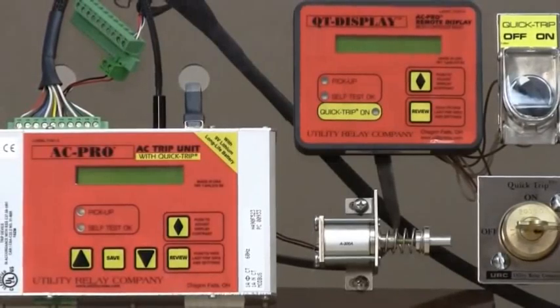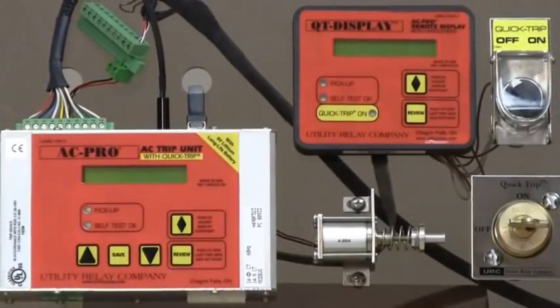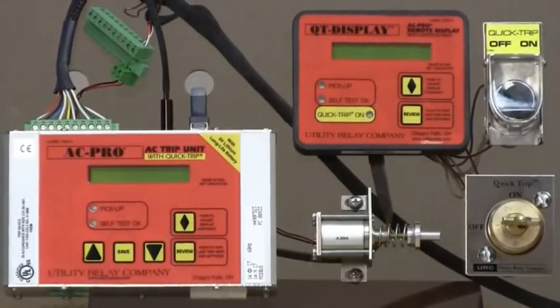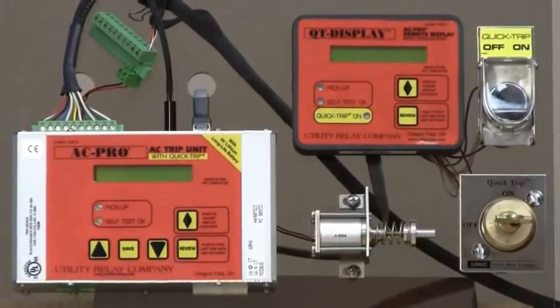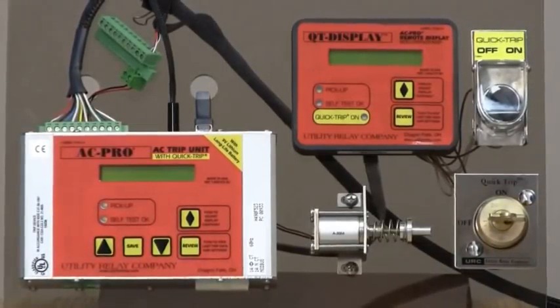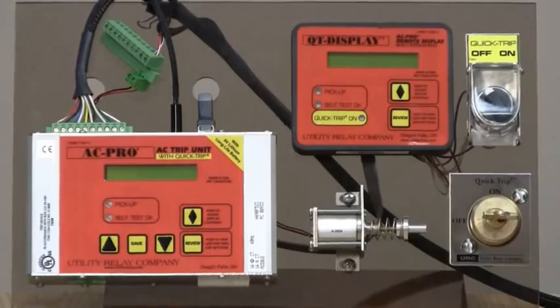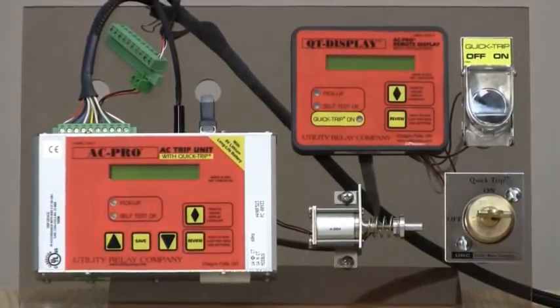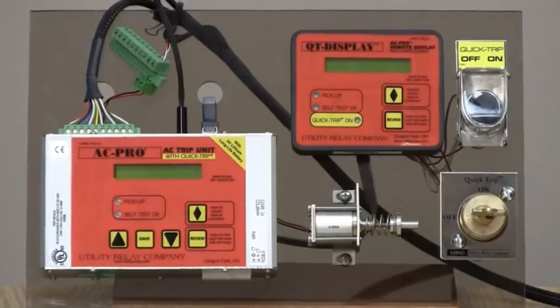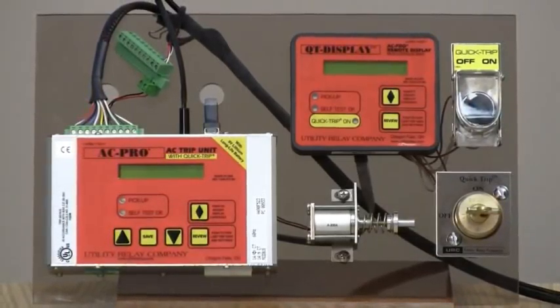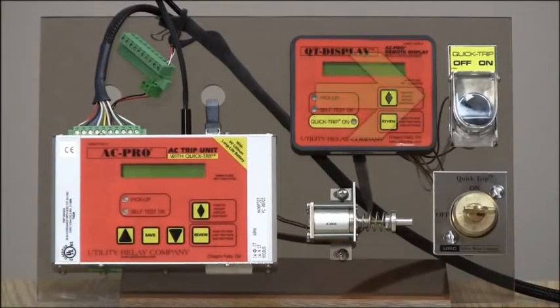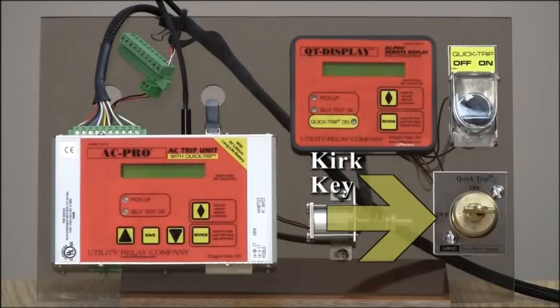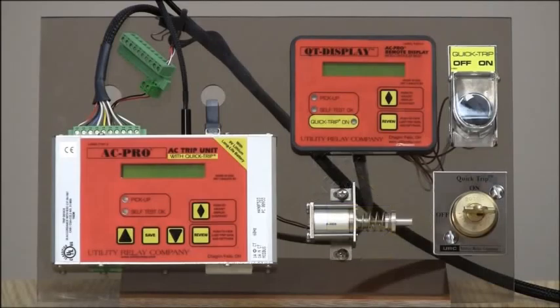I will briefly describe our Quick Trip feature. Quick Trip is used to reduce the arc flash hazard downstream of the breaker. Turning QuickTrip on using the QuickTrip switch turns on the QuickTrip ground fault and QuickTrip instantaneous functions. The instantaneous and ground fault settings that are activated by the QuickTrip switch are another full set of settings, not a fixed percentage. These settings can be chosen based on your arc flash study. The QuickTrip switch can be either our standard switch or the Kirk Key version. The Kirk Key version provides interlocking to ensure the proper use of the QuickTrip arc flash reduction system. The QuickTrip feature is described in full detail in another video.